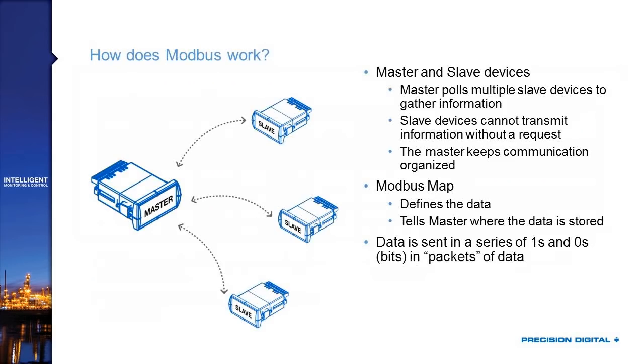Now let's talk about how this actually works. A Modbus system is made up of one master device and slave devices. There can be only one master on a Modbus system, but there can be multiple slaves. The master controls all communication — thinking back to the room-full-of-people analogy, Modbus puts one person at the front of the room as the master, who makes all requests of everyone else and gives everyone else permission to speak.